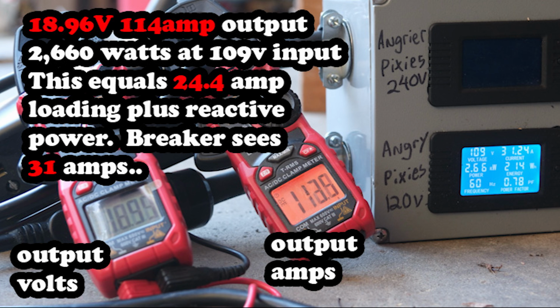Yes, that is correct. It's not an error. 31 amps. Even if its power factor was not 0.78 like the little screen says and it was more like a higher end welder's 1.0, it would still be the 24.425 amp loading. So this device, despite outputting 114 amps, which is under its rated output, actually overloads breakers.